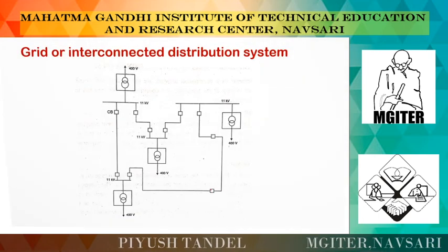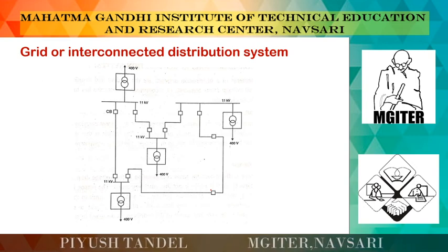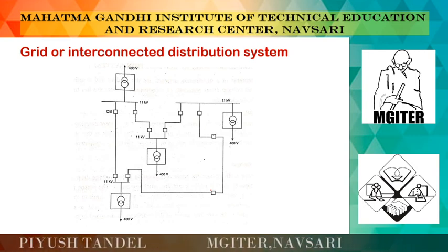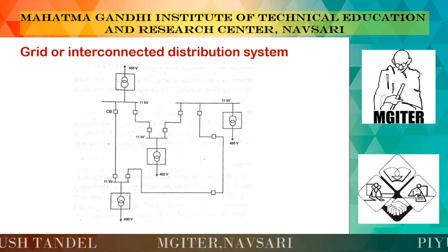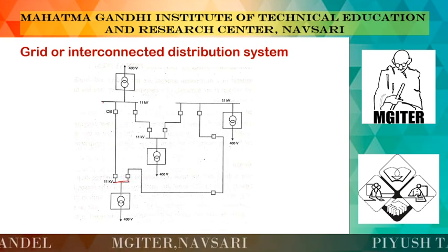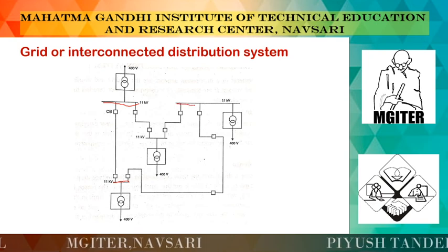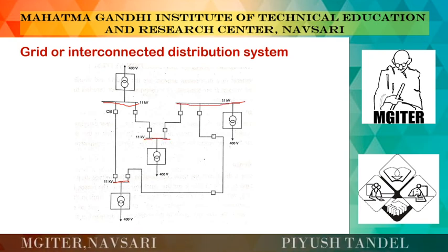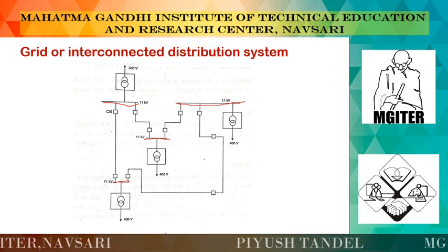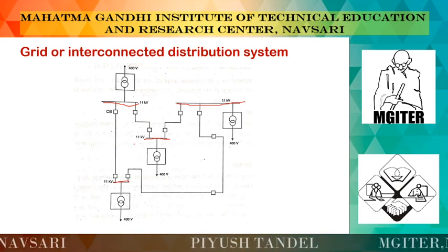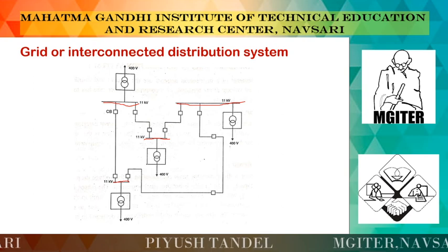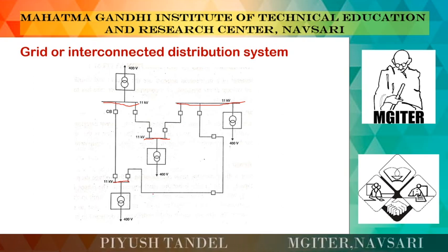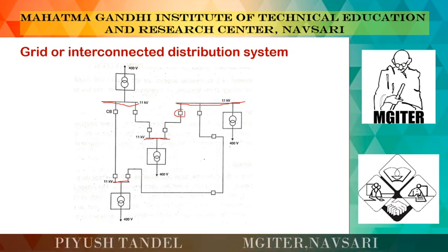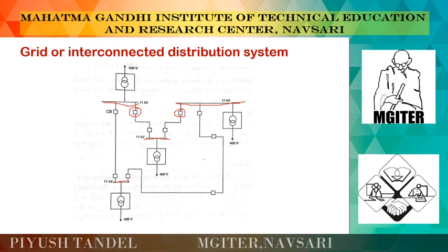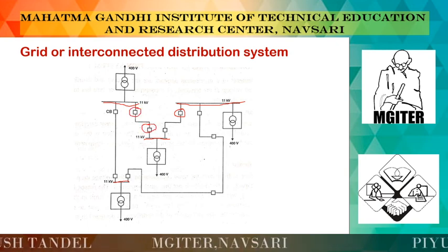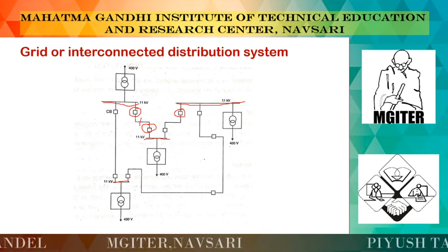Next, or we can say the last one, is the grid or interconnected distribution system. This is the most advantageous and most suitable for distributing power, because we have different 11 kV buses from where we can connect our loads. Whenever a fault occurs on this line or this line, the power flows from the other part. Here the boxes indicate the different circuit breakers available, which isolate the system when a fault occurs in between.